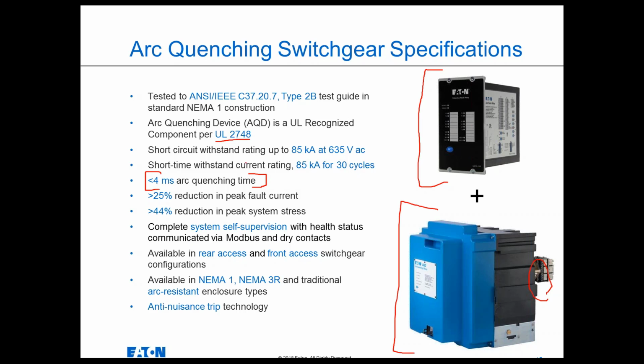So it's extremely fast. As I said, it reduces peak fault current, reduces system stress. Since it's an intelligent and active system, it's able to perform complete system self-supervision, so it's constantly monitoring its health and communicating that out. So if anything goes wrong, the end user will be notified. It's available in every switchgear configuration that Eaton makes. Traditional rear access, that is with the cable compartment in the back. Front access, where essentially we fold the cable compartment around to the front, so you've got a column of breakers, then a cable pull section next to it, then a column of breakers and a cable pull section. So it can be put against the wall, kind of like a switchboard, but maintains a UL 1558 rating.